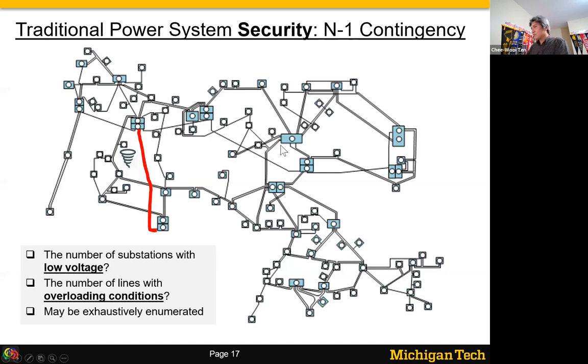To give you a picture, assuming this is the power transmission circuit in a simplified version, you'll see a tornado passing through a certain transmission circuit. We call it N minus one, because in our outage line statement, we take this one out and do a what-if scenario to see the potential problem. The tornado passes through, we run our tool, and make sure the voltage is within range and that other parts of the network are not overloaded. Overload is never good because it can implicate a lot of potential cascading problems.